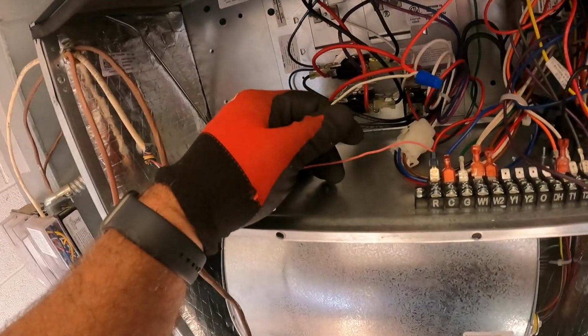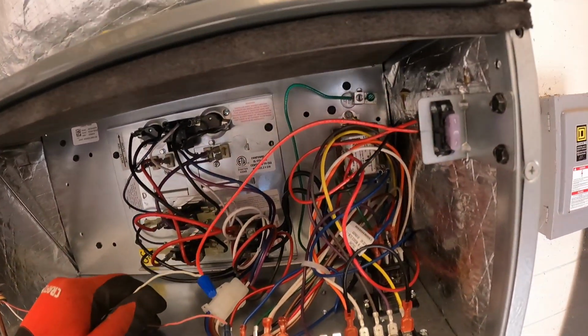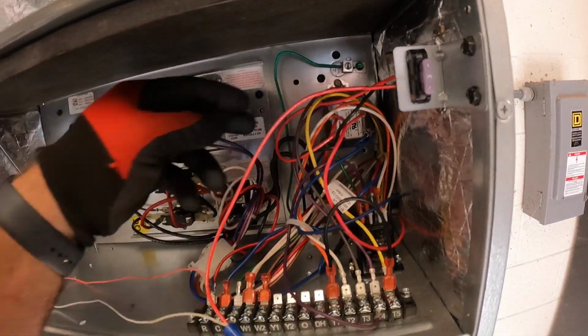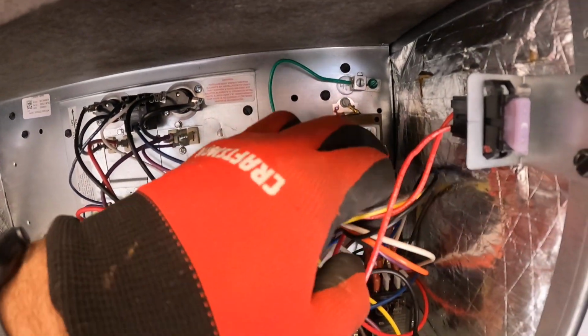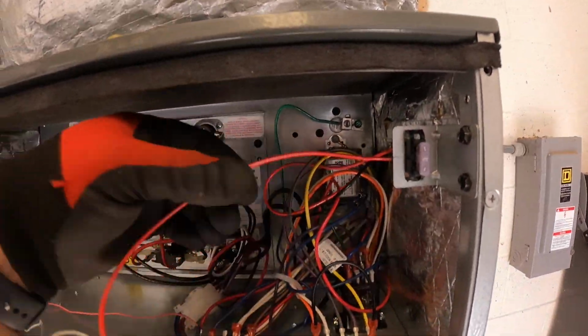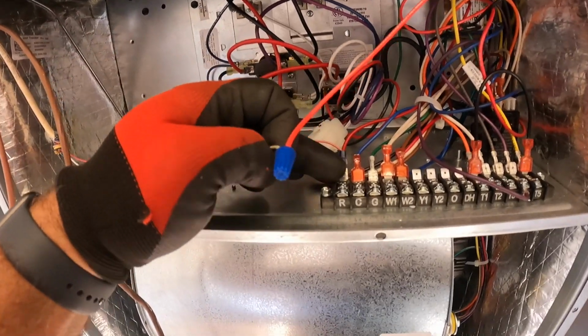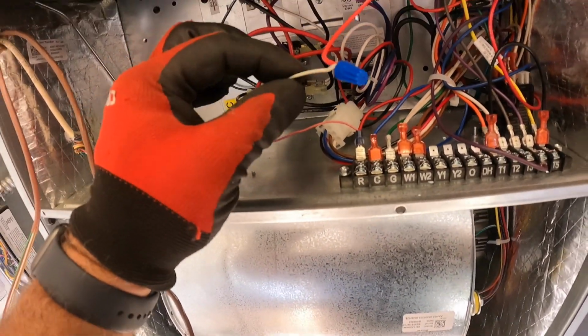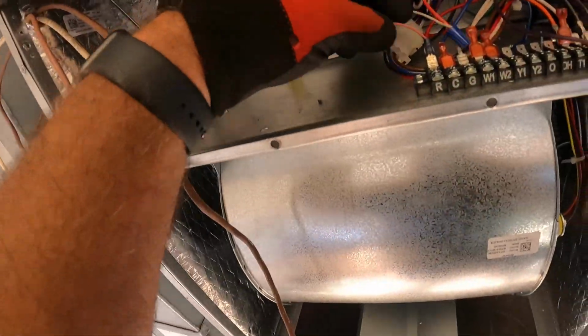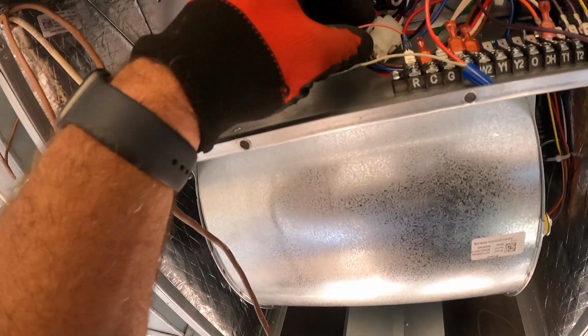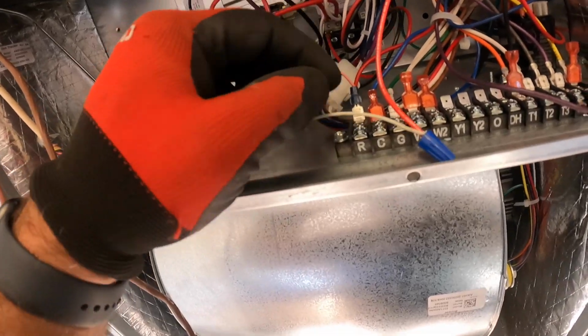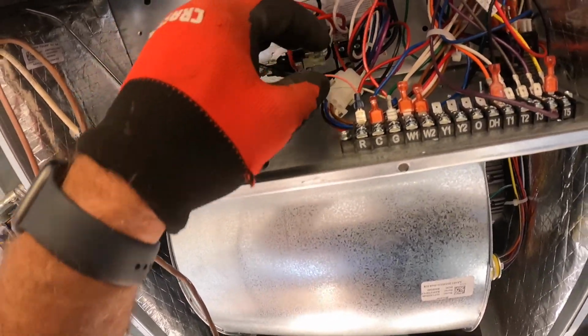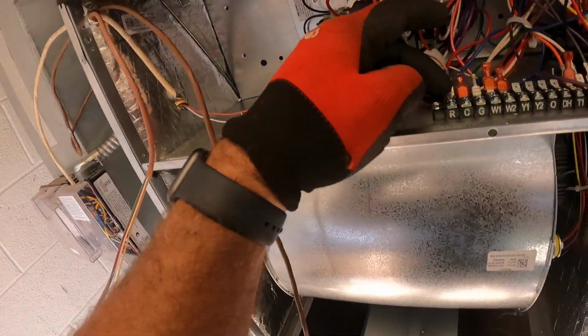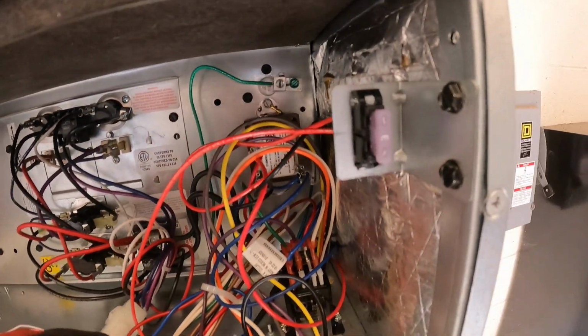Here's how we're going to integrate the smoke detector. It was using this red and white wire, and before it was after the fuse on that Trane. This comes out of the transformer off the 24 volt, up to the fuse, through the fuse, and down here. This used to be plugged on at the red strip on the terminal. I just cut the spade off and wire nutted it to the white. That goes over to that relay and comes back on the red. This is stranded wire, so I crimped on a little terminal. So we're back in business here. As long as that smoke detector says it's okay, we should get red to here, as long as the transformer's good and the fuse is good.